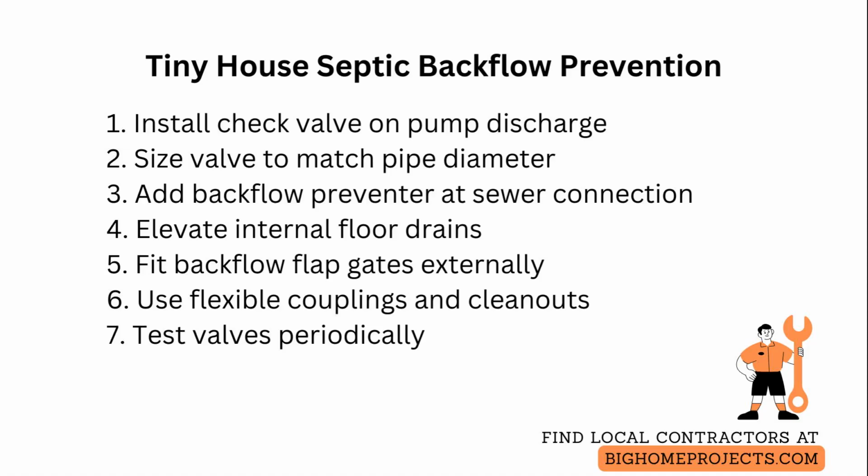Fit backflow flap gates on exterior drainage inlets to protect against storm surge and surface runoff entering the septic inlet or house drains during heavy rain events. Use flexible couplings and accessible cleanouts on both sides of valves so you can clear blockages without cutting pipe and so maintenance can be performed quickly.